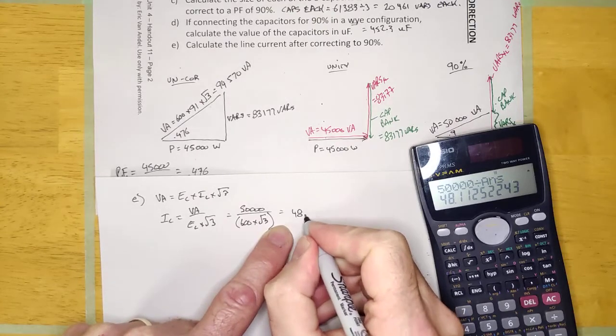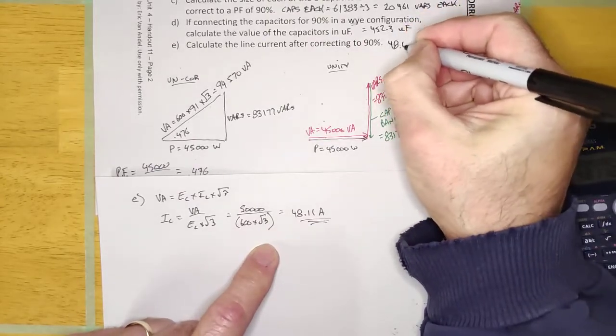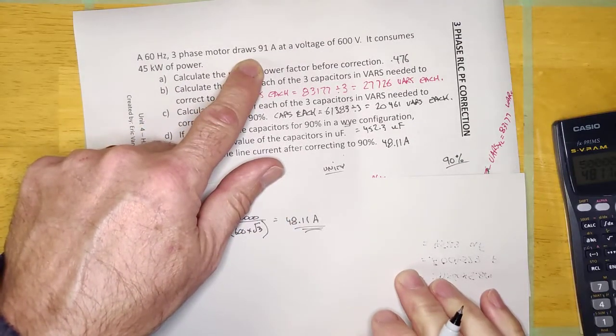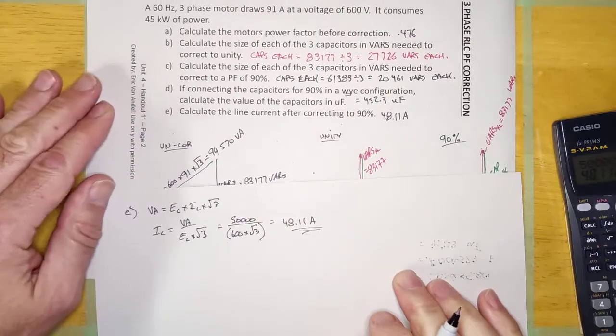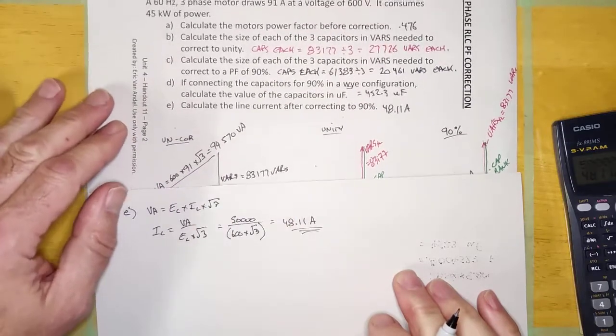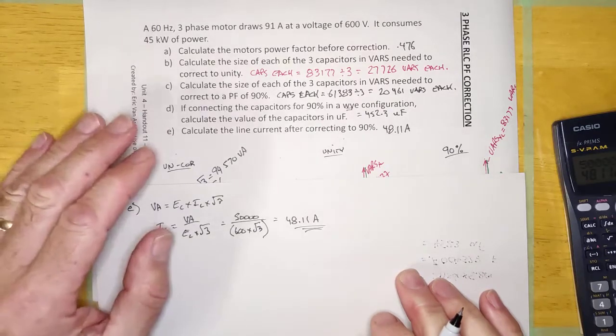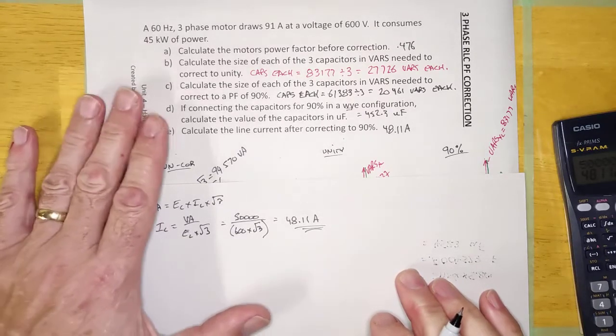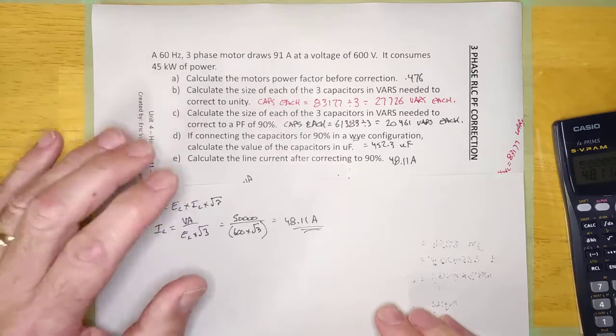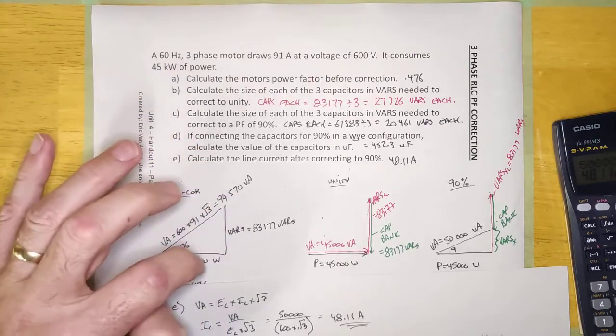After correction, 48.11 amps. Now, this thing was drawing 91 amps before correction. We've corrected it. It's drawing 48.11 amps now when I've corrected it to 90%. If I calculated it at Unity, it'd be even lower. But the thing to remember is to do it the same way you do it in single phase. You're going to draw an uncorrected power phasor diagram, remembering that it's three-phase. Finish the drawing completely up, and then draw a corrected phasor diagram.